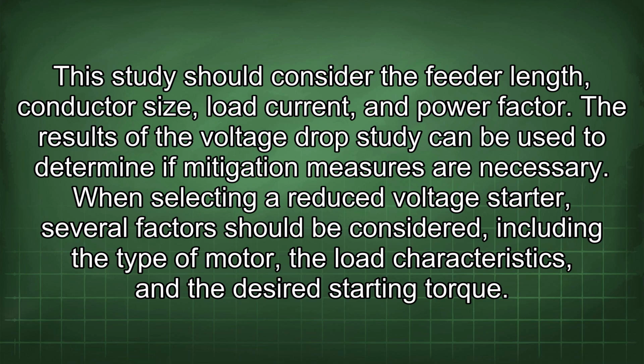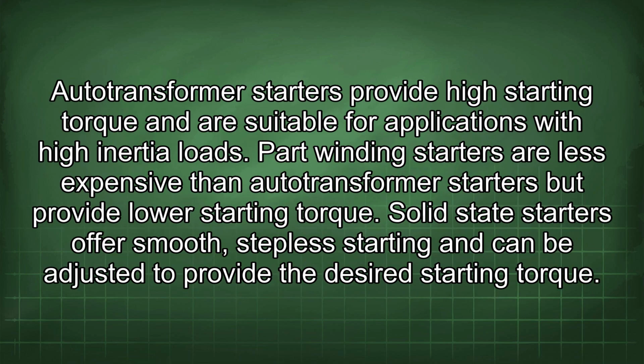When selecting a reduced voltage starter, several factors should be considered, including the type of motor, the load characteristics, and the desired starting torque. Autotransformer starters provide high starting torque and are suitable for applications with high inertia loads. Part winding starters are less expensive than autotransformer starters but provide lower starting torque. Solid-state starters offer smooth, stepless starting and can be adjusted to provide the desired starting torque.